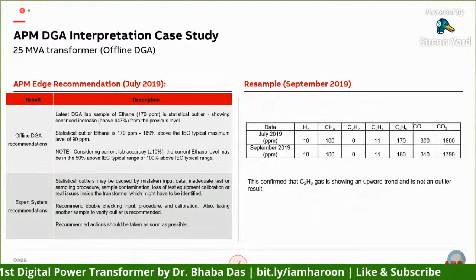That recommendation we passed on to the customer and said, please double check, please redo your offline DGA. And they came back and said, okay, they did the test in 2019, and this confirmed that the gas is actually going up and the result is not an outlier. We re-uploaded the confirmation sample, and the software recommended that yes, it is actually above 50% of the IEC gas levels, and based on the full 5 offline DGA samples, we are showing an increasing rate of 60 ppm per year.